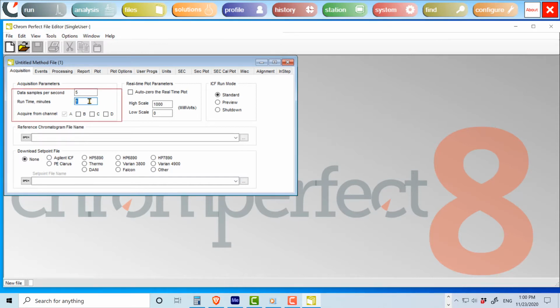The runtime determines how long acquisition will take place. It need only be somewhat greater than the retention time of the last peak of interest. The sample rate determines how often the software reads the detector signal. The chromatographer's rule of thumb is that there should be at least 10 data points across the full width of the narrowest peak of interest. If you don't know, enter 20 for a GC or 5 for an LC.